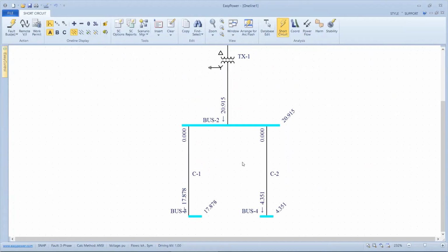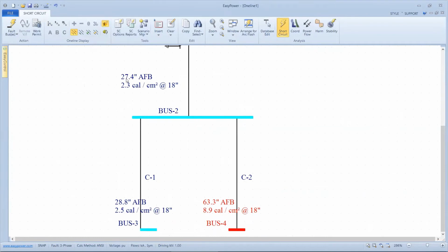He said, now I'm ready to calculate incident energy. The incident energy icon is this little burning man symbol on the top row. And once I click on that, I get new numbers and new colors. And he said, Jim, this is where I have a problem with EasyPower. I said, well, what are you talking about? He says, right here on the transformer secondary, I see an arc flash boundary of 27.4 inches with an incident energy of 2.3 calories per square centimeter at a working distance of 18 inches.